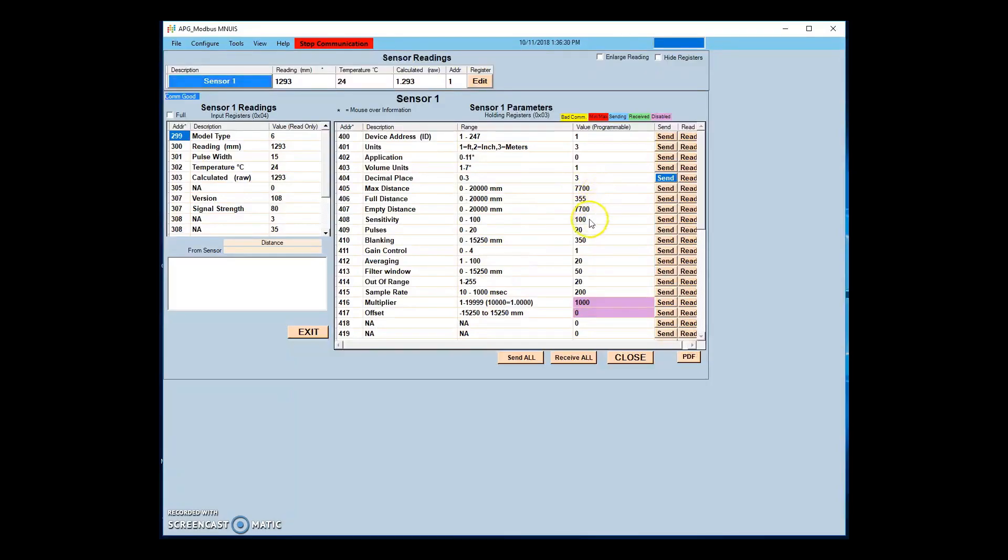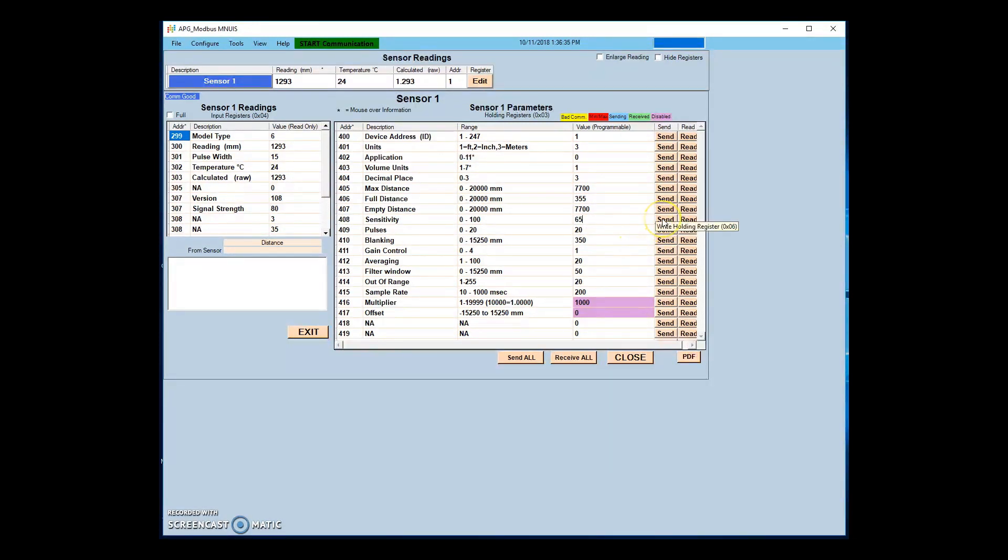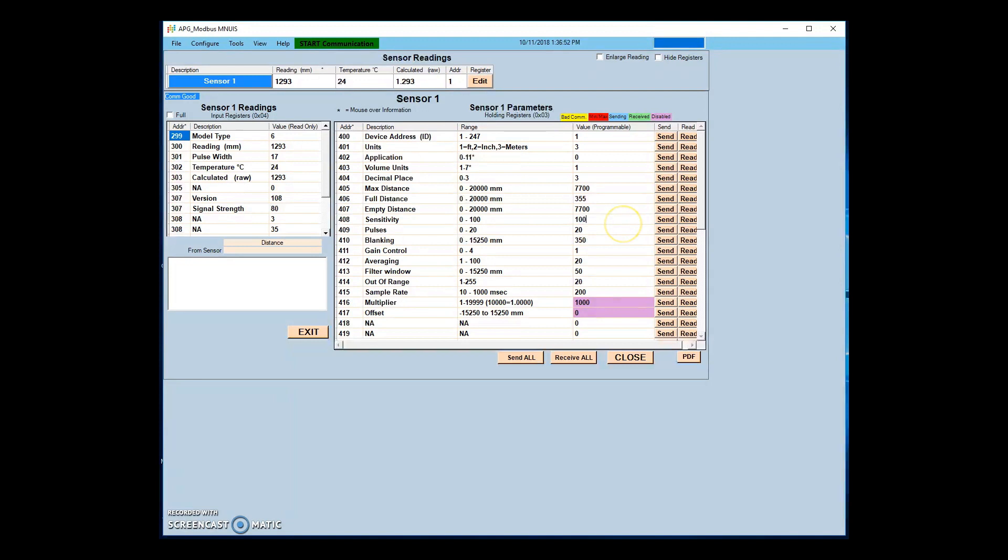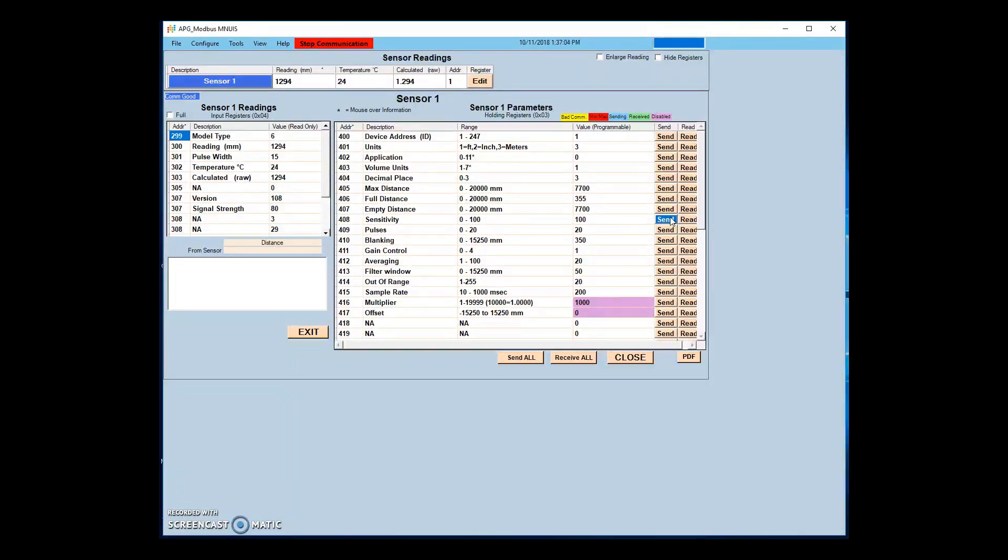Sensitivity sets the level of gain applied to the sensor signal. In AutoSense, HardTarget, or SoftTarget modes, the parameter sets an upper limit to the gain that can be applied. If the sensor is operated in Manual mode, this value will set the gain value. If using Manual mode, it is recommended to determine the minimum gain value that will allow the target to be reliably tracked through the full range of expected conditions. This will save power and extend the life of the sensor.